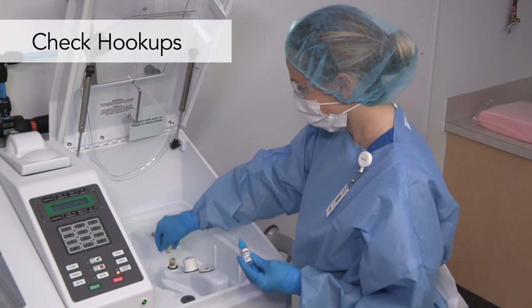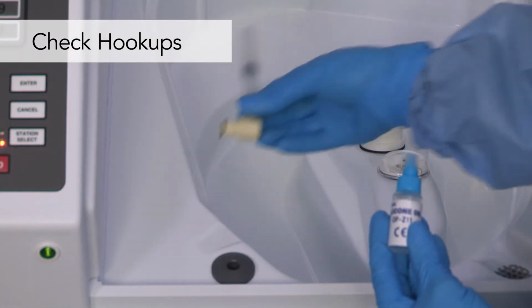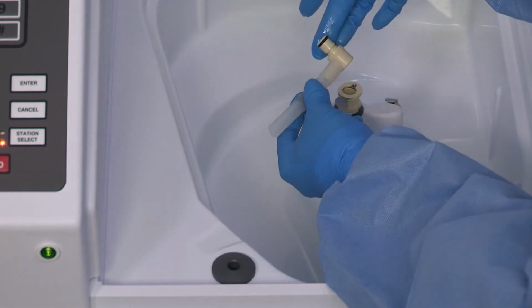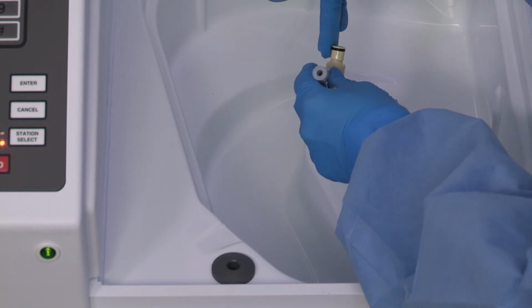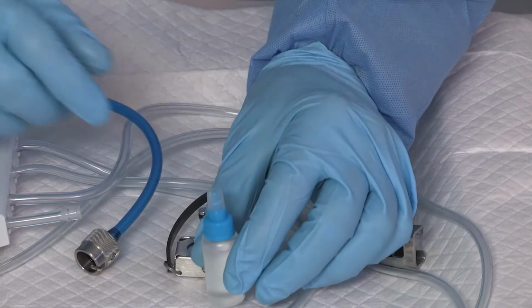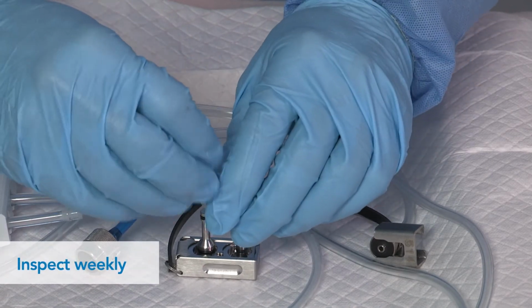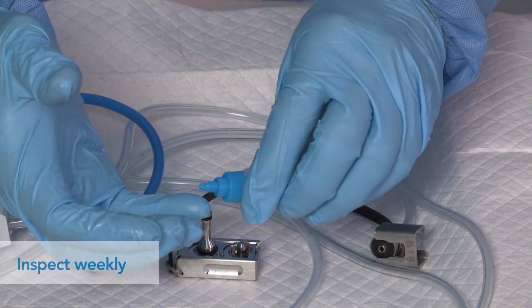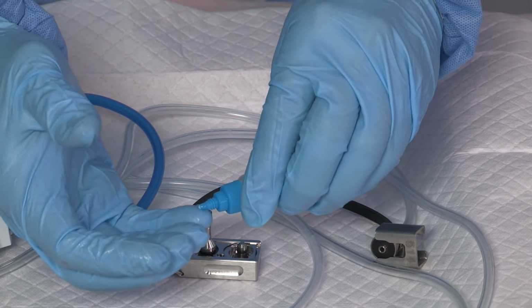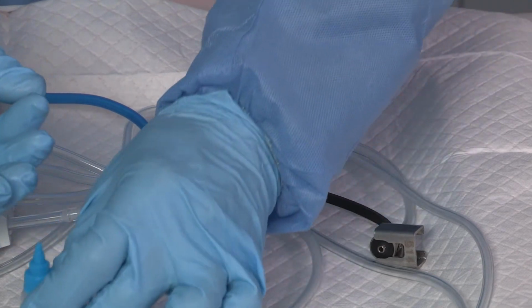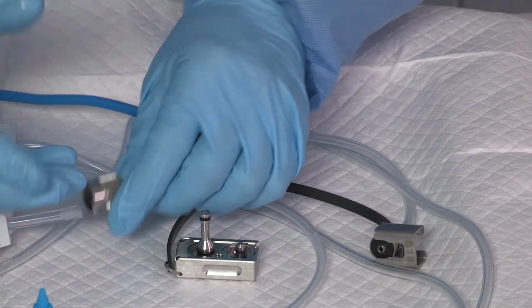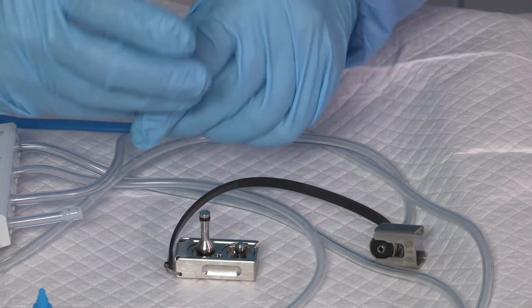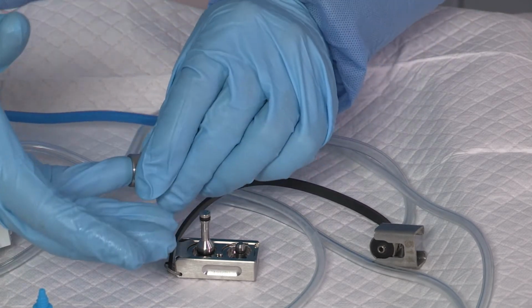To maintain the hookup O-rings, on a weekly basis, inspect the O-rings in the hookups for damage, nicks, and cuts. If an O-ring is damaged or missing, take the hookup out of service. Lubricate the O-rings by placing a small amount of silicone oil between your gloved thumb and finger and spreading evenly on all hookup O-rings and quick connector.